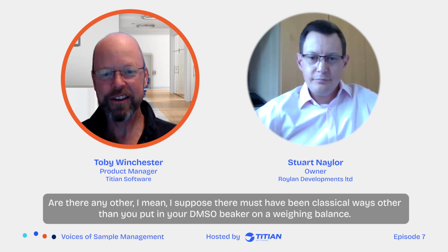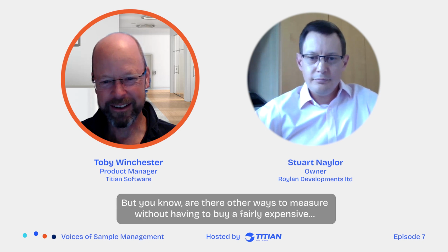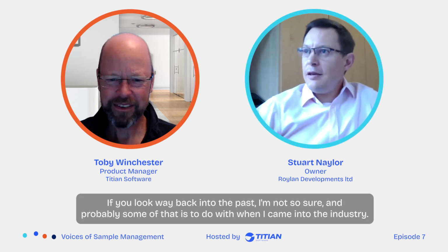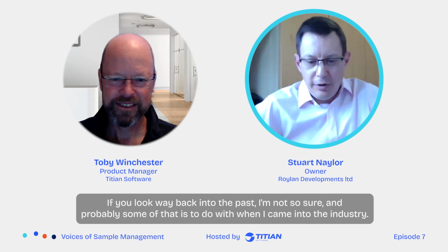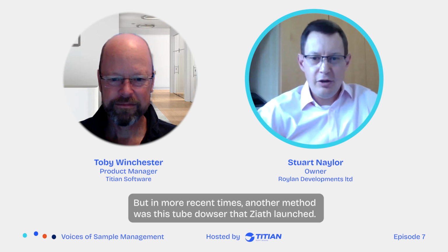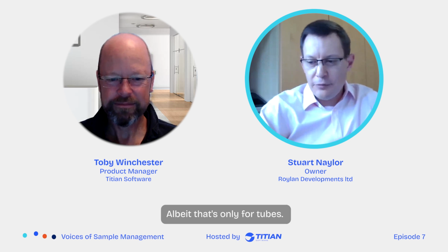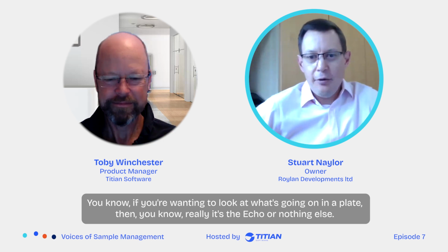I suppose we've talked a little about the echo measuring hydration. Are there any other ways? I suppose there must have been classical ways other than putting your DMSO beaker on a weighing balance. But are there other ways to measure without having to buy a fairly expensive instrument? If you look way back into the past, I'm not so sure, and that's probably to do with when I came into the industry. But in more recent times, another method was this tube dowser that Ziath launched. Albeit that's only for tubes. If you're wanting to look at what's going on in a plate, then really it's the echo or nothing else.